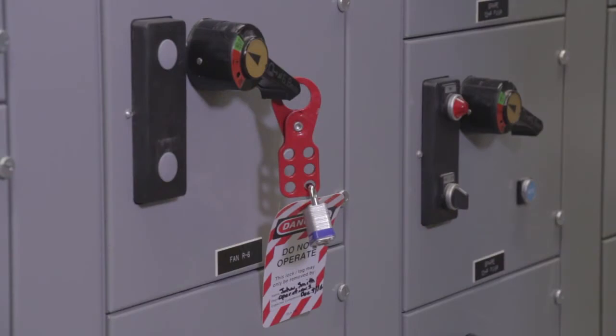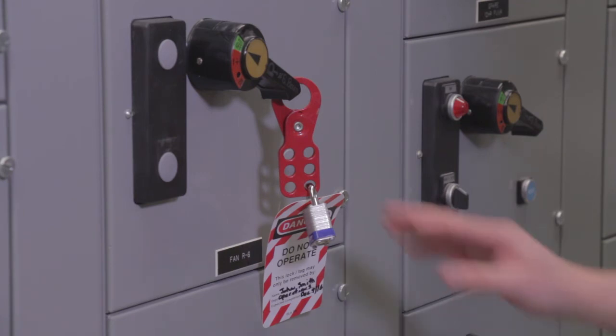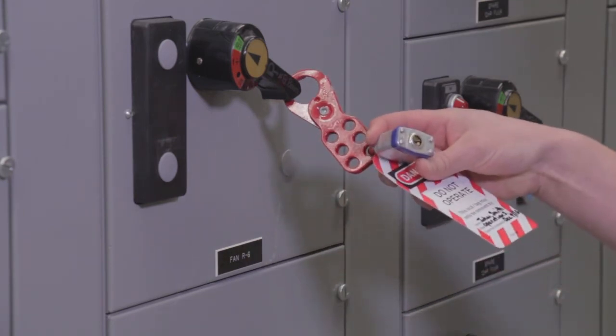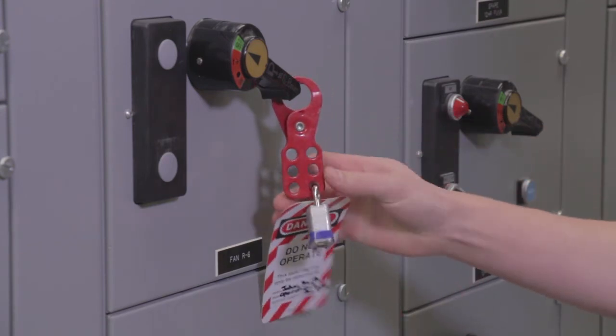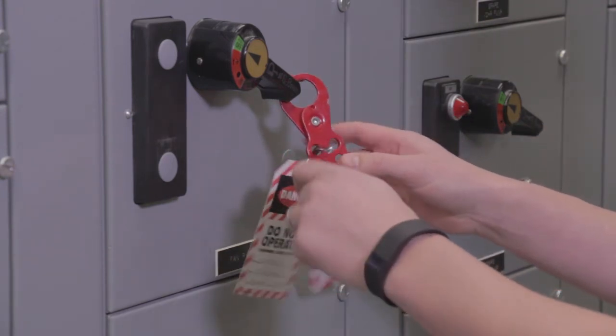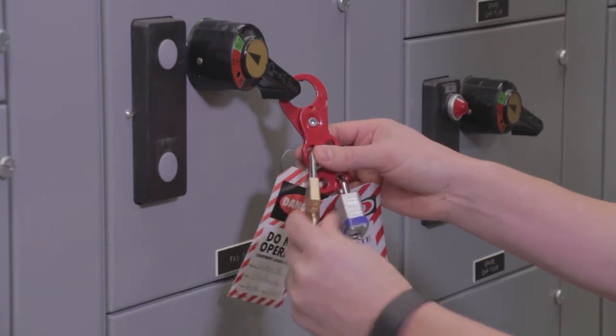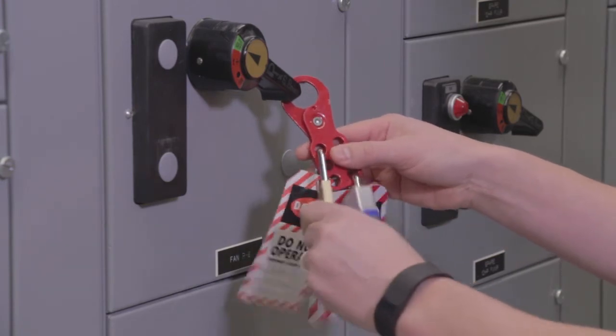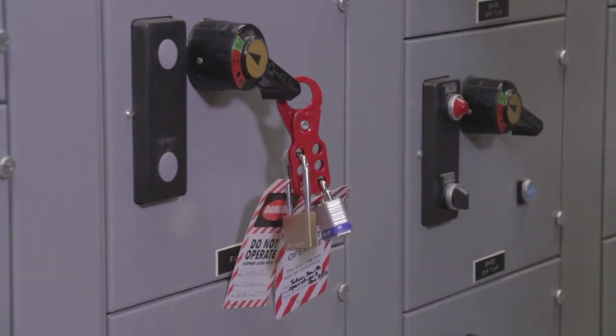There are times when multiple lockout devices need to be applied to a control point or piece of equipment. Occasionally, a contractor or board maintenance staff will be required to perform testing, maintenance, or service, and will assume control of the lockout. At times, multiple contractors, such as a plumber and electrician working together, may need to service an item that was locked out.